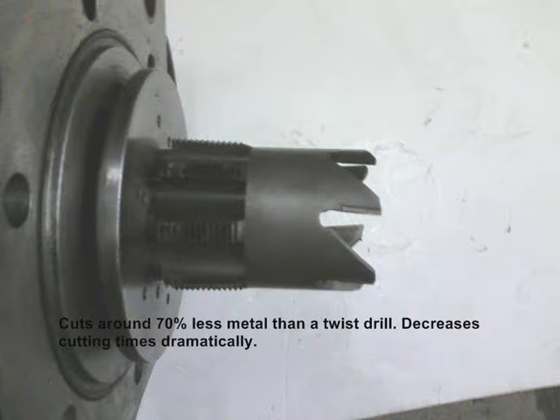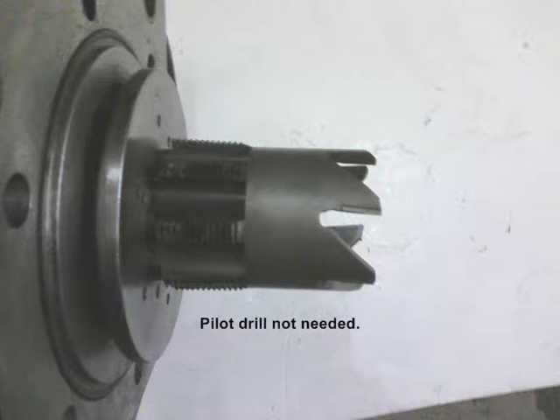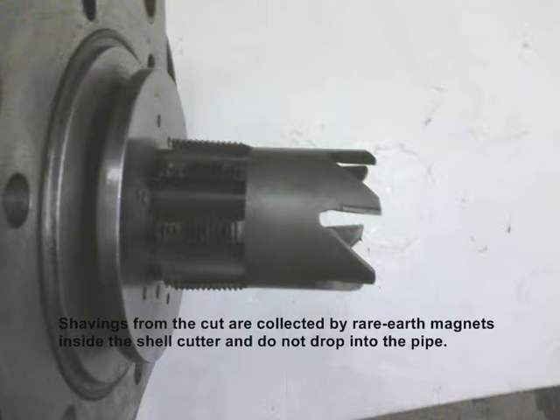so it cuts around 70% less metal than a twist drill. This decreases cutting times dramatically. A pilot drill is not needed, since the equipment is designed to ensure automatic alignment.